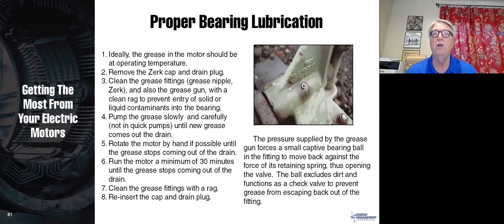Pump the grease slowly and carefully. Please pump grease slowly. It takes time for it to flow through the bearings. If you pump it too fast, you may pump it out the seals, or it may not go through the whole bearing. Keep pumping until grease comes out the drain. Now remember up there in number two, we need to remove the drain plug. If you don't remove the drain plug, you are simply pushing that grease through the seals and into the middle of the motor, into the air gap, and it's going to have premature failure.